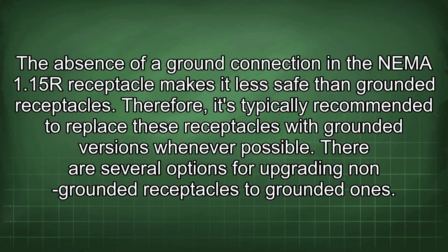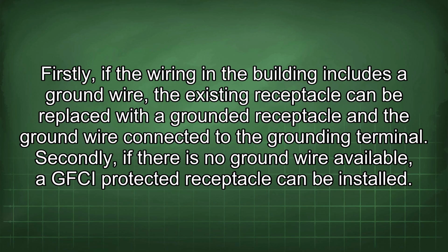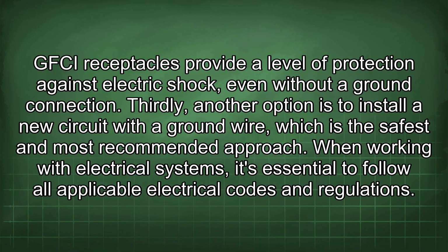There are several options for upgrading non-grounded receptacles to grounded ones. Firstly, if the wiring in the building includes a ground wire, the existing receptacle can be replaced with a grounded receptacle and the ground wire connected to the grounding terminal. Secondly, if there is no ground wire available, a GFCI protected receptacle can be installed. GFCI receptacles provide a level of protection against electric shock, even without a ground connection. Thirdly, another option is to install a new circuit with a ground wire, which is the safest and most recommended approach.